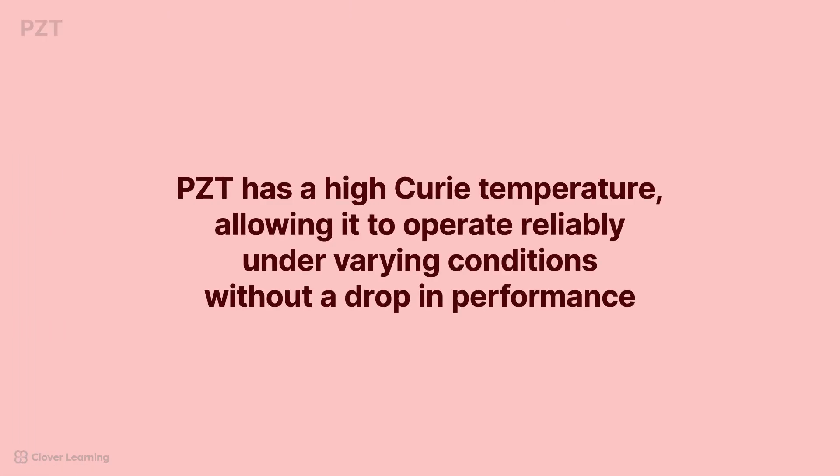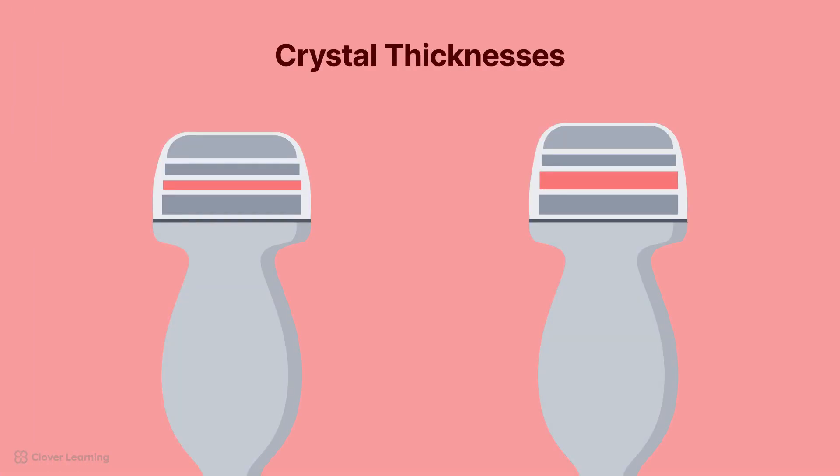PZT specifically is a good choice for the piezoelectric crystal because it has a higher Curie temperature, which is the temperature above which piezoelectric properties are lost. This allows it to operate reliably under varying environmental and clinical conditions without a drop in performance. You should also note that the piezoelectric crystal comes in different thicknesses, which affects its imaging ability.